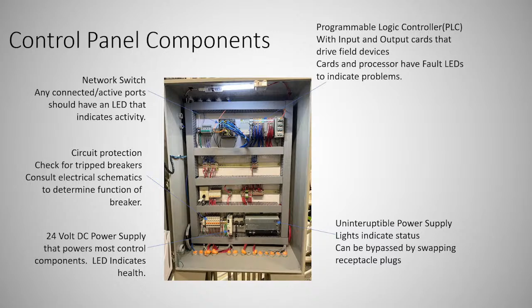I had a separate slide on here, a note on UPSs. A lot of places will designate, we need to have 6 hours of backup power on our UPS to keep a PLC running. Well, when you lose power to your site, you've lost all your valves, you've lost all your pumps, you can't do anything. The only thing a UPS is going to be able to do is let you see instrumentation, levels, and what's going on, but you're still not going to be able to control anything. In my mind, you want to protect electronics with a UPS in case you have brownouts or whatever.